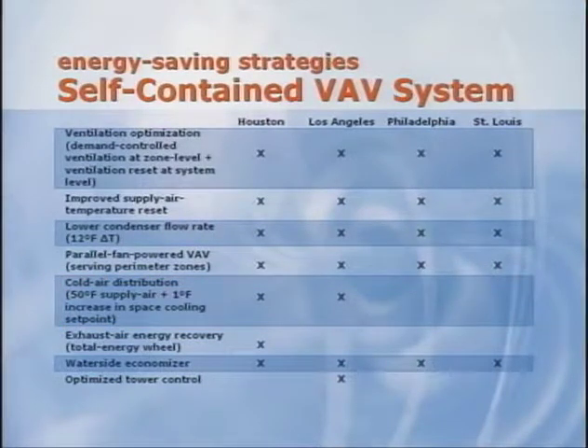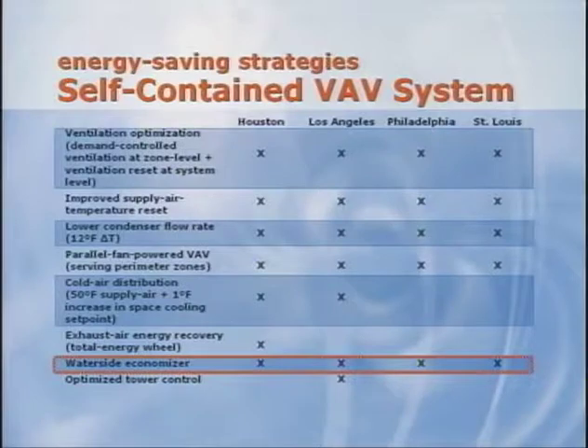Some of the differences stem from the fact that this system includes a condenser water loop. First, the condenser water system was designed for a lower flow rate, 2.5 GPM per ton, versus the past conventional practice of 3 GPM per ton, and the self-contained units were equipped with water-side economizer coils, which use the cool condenser water for pre-cooling when conditions permit. Finally, a total energy wheel was used to precondition the entering outdoor air for the proposed building in Houston. This strategy not only saves energy, but also allows for a significant reduction in equipment cooling capacity.